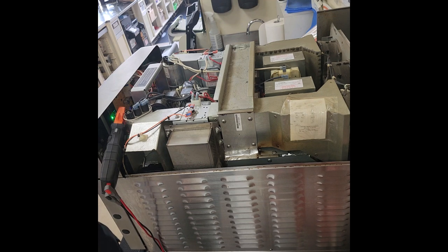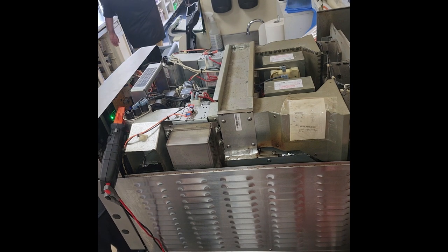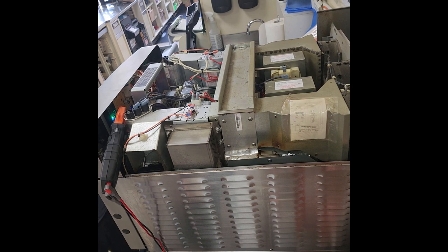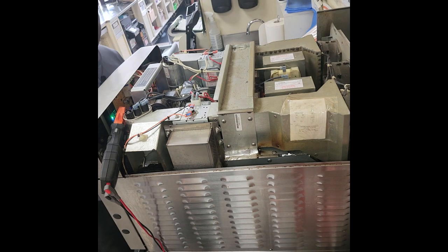First, before I do that, I'm going to test the door switch, to make sure the door switches are working right. If you watch some of the other videos we've done, you can see the door test, where you have the primary, secondary, and monitor switch. The monitor switch is on the right side, and the secondary and primary switches are on the left side. You want to make sure those switches go in sequence: primary, secondary, monitor when opening, and monitor, secondary, primary when closing.